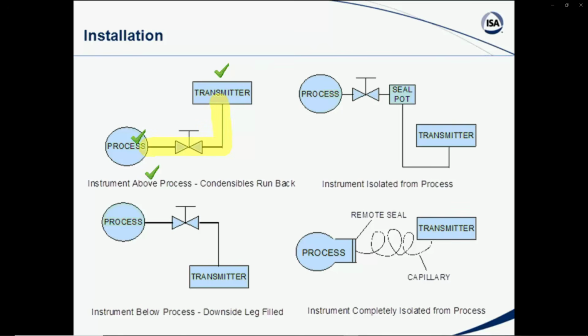So this would be on gas or vapors, assuming that the temperature or the corrosivity of that measured fluid is not detrimental to the transmitter. Okay? If it is detrimental to the transmitter, you would need to revert to some sort of isolation. For instance, here the process is isolated via a sealed pot and a liquid-filled lead going down to the transmitter, and that allows us to seal off from the process to our transmitter if we have some sort of temperature or corrosivity. Also, this type of measure would be used for steam flow, for instance, to isolate the steam vapors from our transmitter so that we did not have to use some unique type of metal constitution on our transmitter.